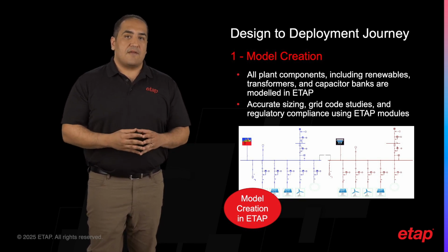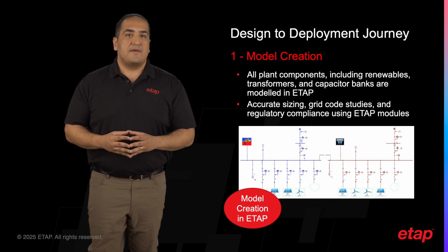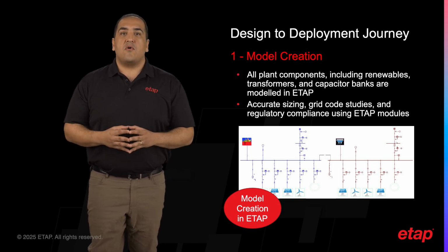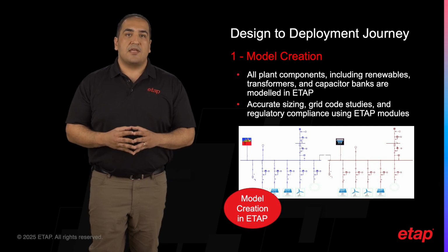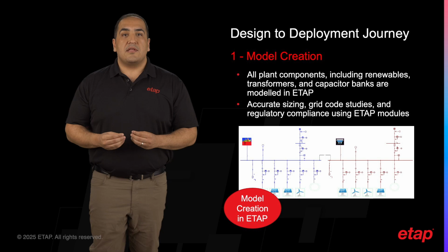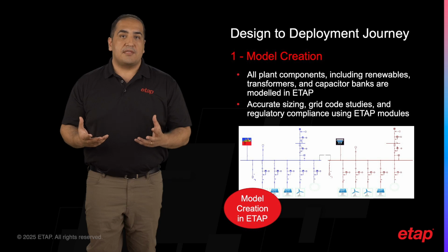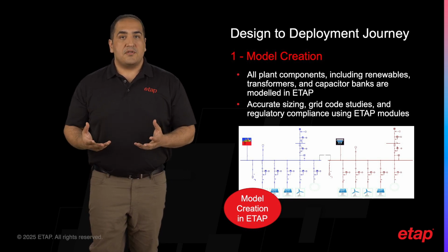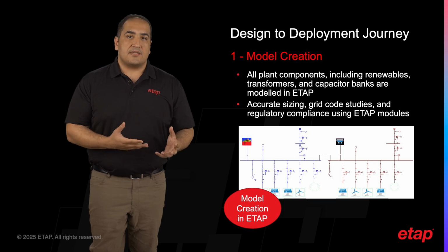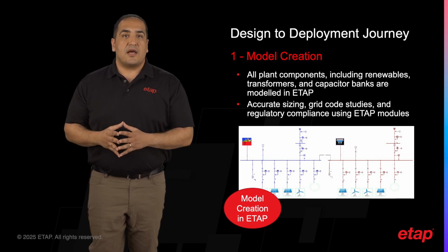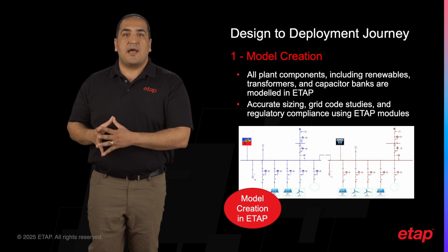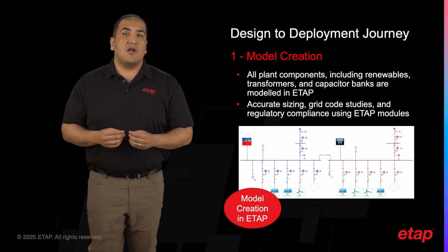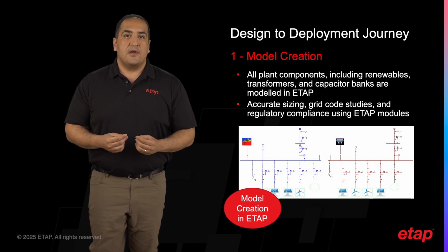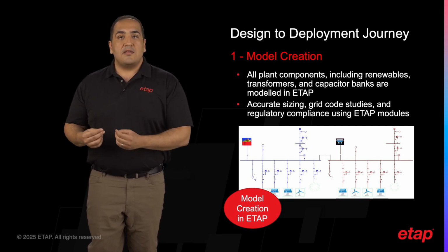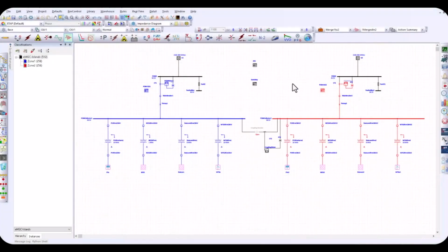It begins with the design phase, where every component in the plant, whether renewables, transformers, or capacitor banks, is meticulously modeled in ETAP. This comprehensive modeling includes not just the physical attributes, but also the settings and operational capabilities of each element. Various ETAP modules, such as load flow and transient stability studies, are employed to accurately size the assets, ensuring that they meet the demands of the plant. Grid code studies are also conducted within ETAP at this stage to verify that the plant complies with all necessary regulations. Now let's take a look at how it works.